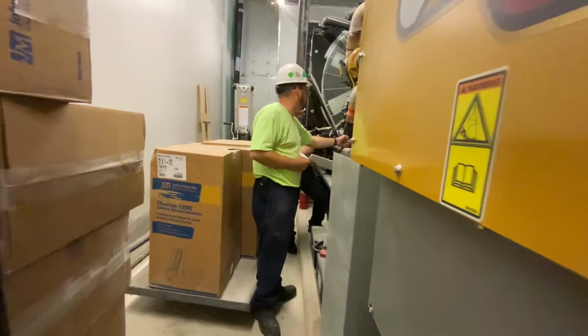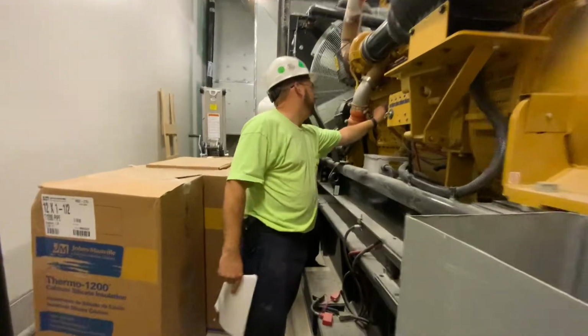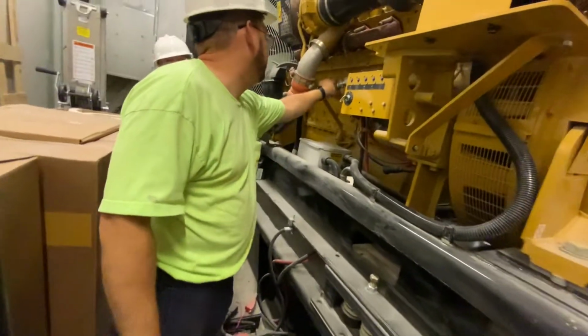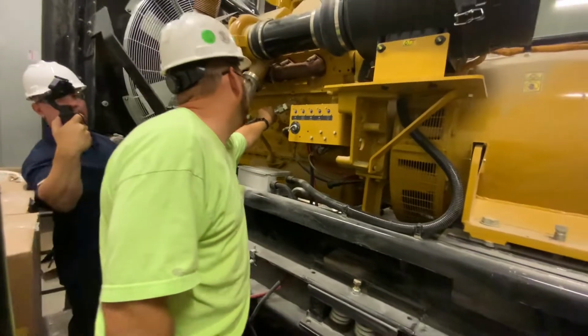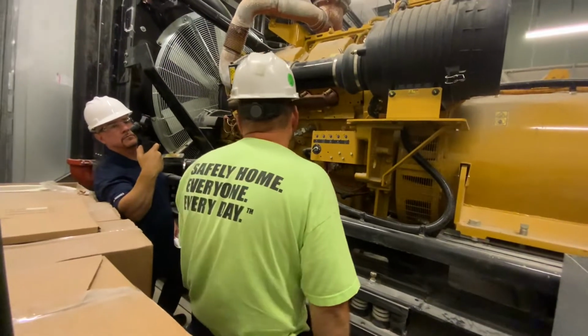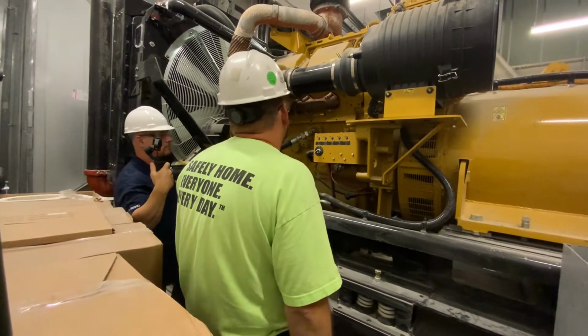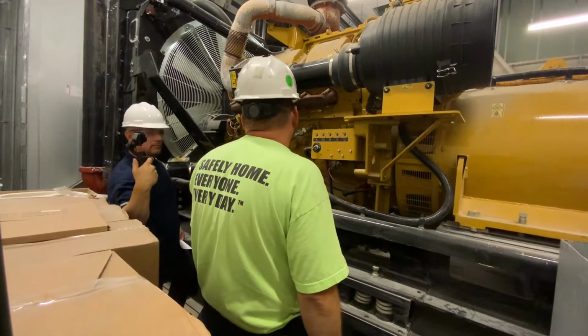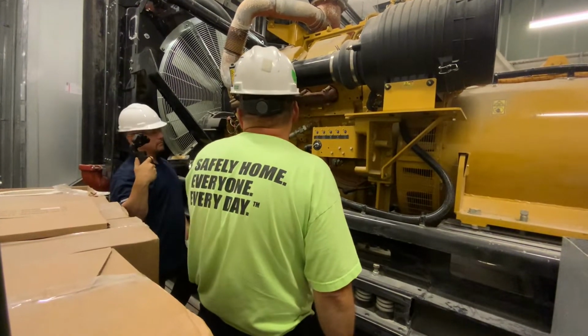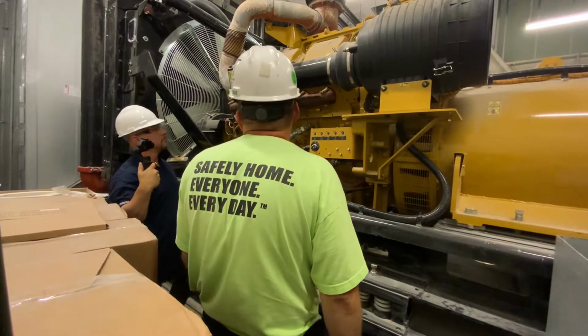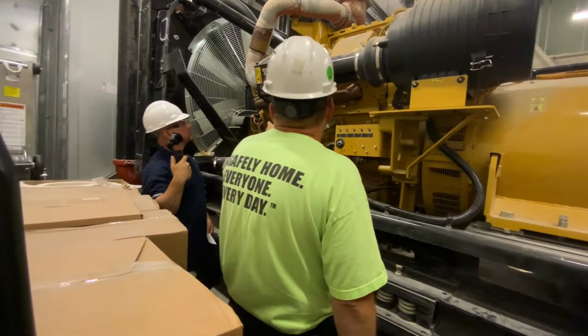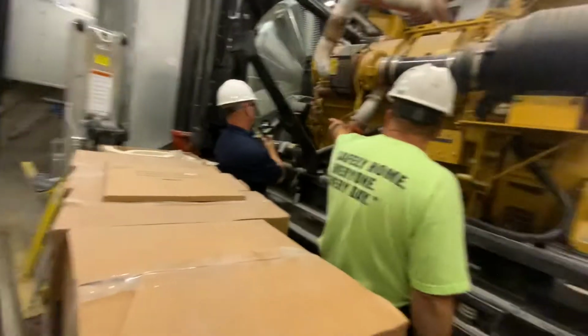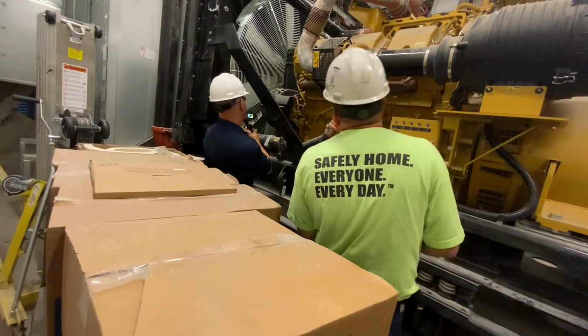Your jacket water heater is right here. It does have a circulating pump on there, so the line's not going to be anywhere near as hot as it has been in years past. You can hold your hand on there. It's only about maybe 130 degrees coming out of there. It's always a good idea, when you're doing weekly inspections or whatever, to grab that upper line, make sure it's still hot. You get your alternator right up front there.